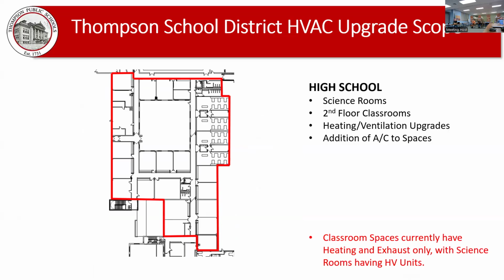The science rooms for the high school, as well as the second floor classrooms, is a large area. Right now it's very minimal in regards to ventilation - it's an exhaust-only type system, so you're basically getting makeup air through infiltration, cracks, and air moved throughout the school. There is no supply air in this area. The science classrooms do have units that provide supply, return, and exhaust, which by code requires 100% outside air for science classrooms. So the science classrooms will be more of an in-kind replacement of what they currently have, with full ventilation and fresh air exhaust. The rest of the space will get 3 new units providing supply air, return air, and full ventilation, so you're going to get outside air and be code compliant.